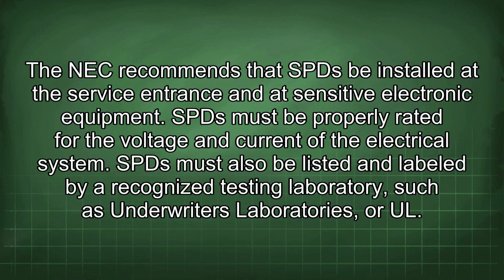The NEC recommends that SPDs be installed at the service entrance and at sensitive electronic equipment. SPDs must be properly rated for the voltage and current of the electrical system. SPDs must also be listed and labeled by a recognized testing laboratory such as Underwriters Laboratories, or UL.